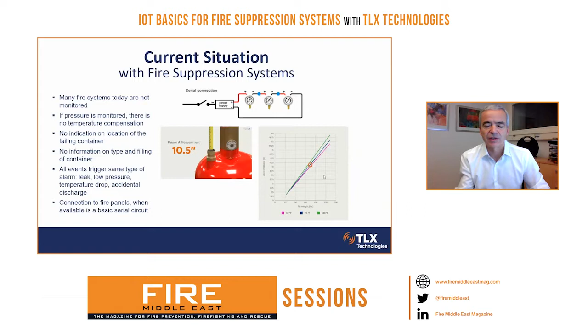If one of those tanks is at low pressure, we just get an indication that something is wrong with that circuit. All failures in a system today provoke the same type of alarm, so a technician needs to go on site and explore what the failure is. Has there been an accidental discharge and all the cylinders are empty, or is it just one cylinder that's low pressure? All events produce the same type of alarm.